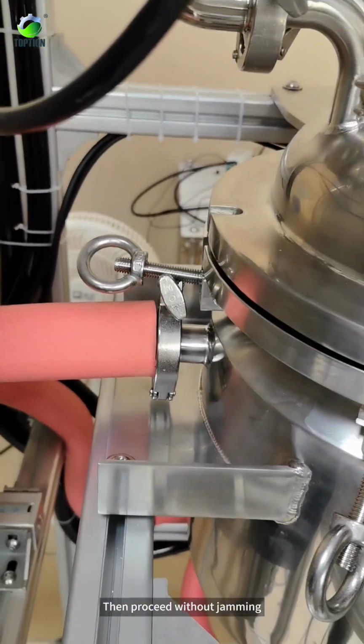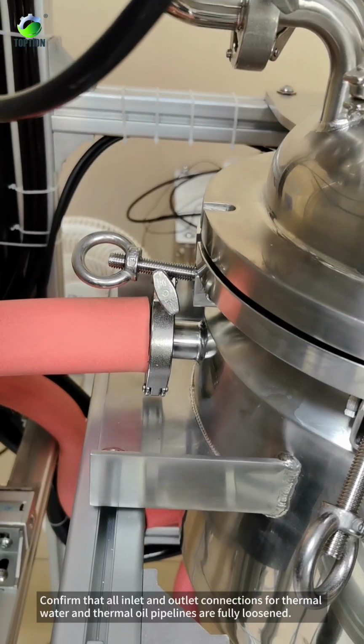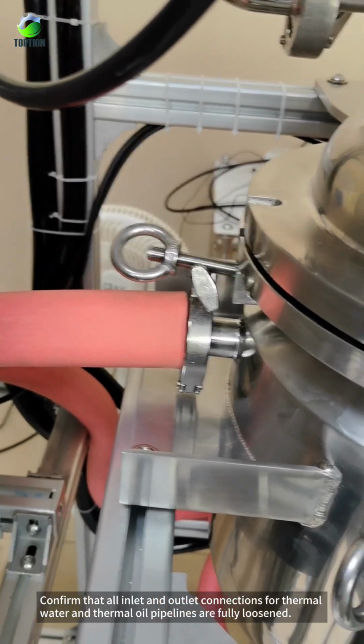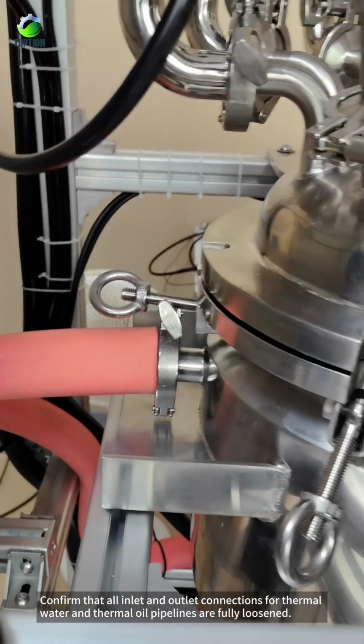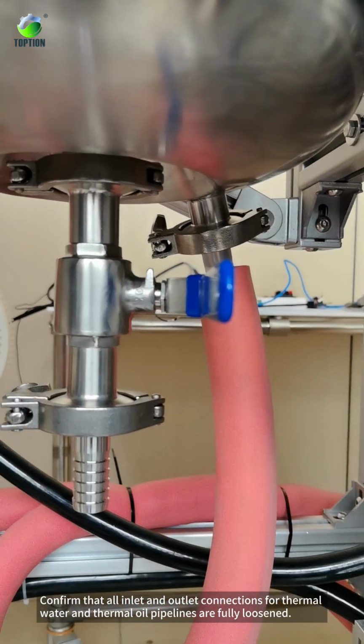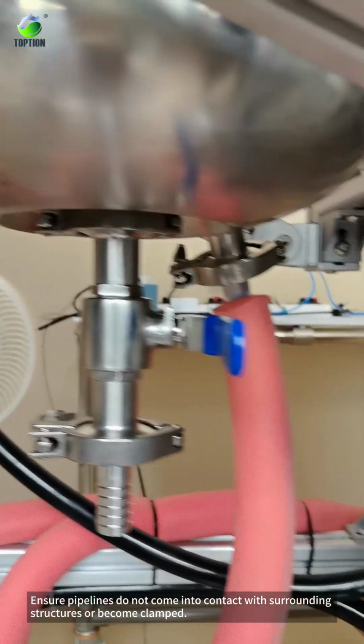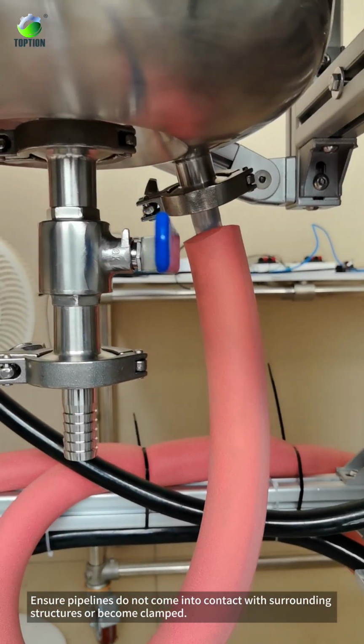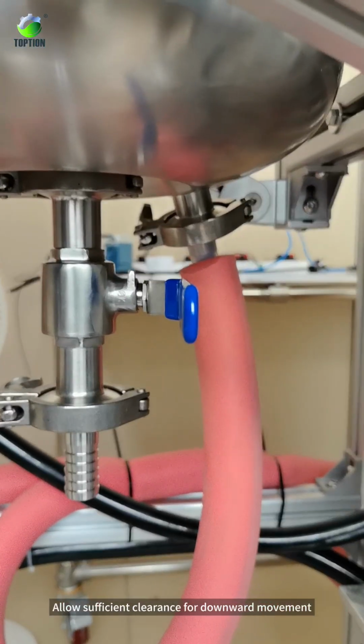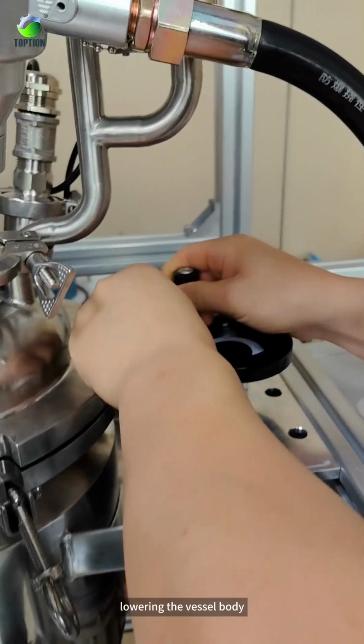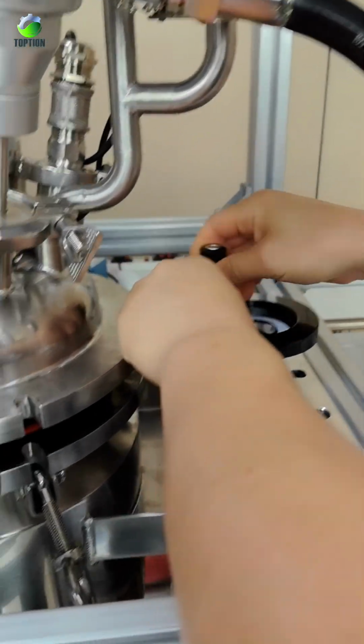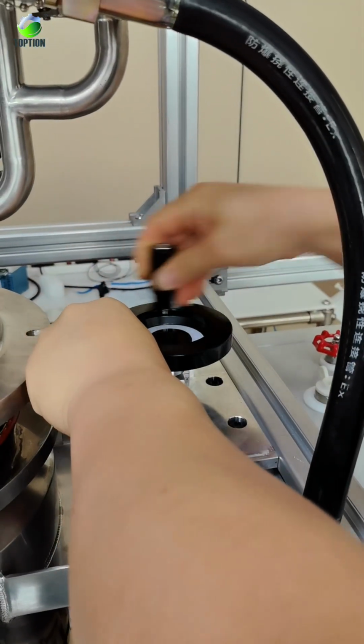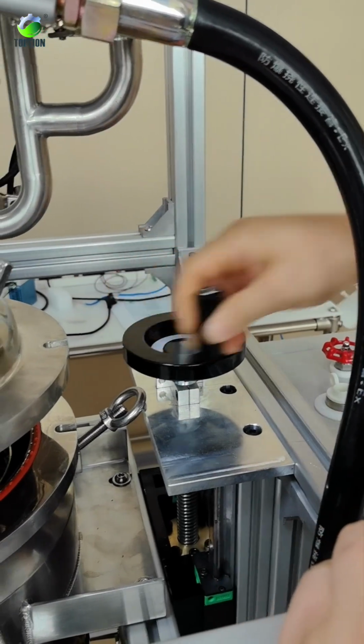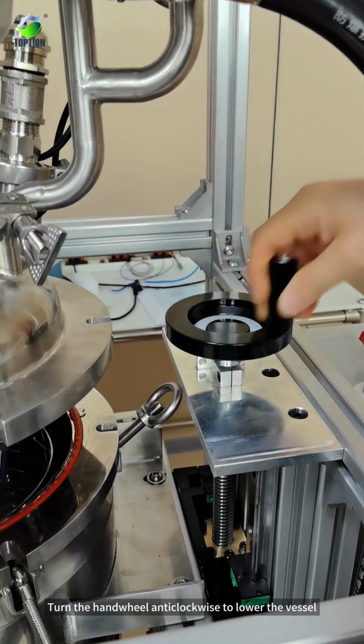Then proceed without jamming. Confirm that all inlet and outlet connections for thermal, water, and thermal oil pipelines are fully loosened. Ensure pipelines do not come into contact with surrounding structures or become clamped. Allow sufficient clearance for downward movement. Now begin turning the hand wheel, lowering the vessel body. Turn the hand wheel anti-clockwise to lower the vessel.